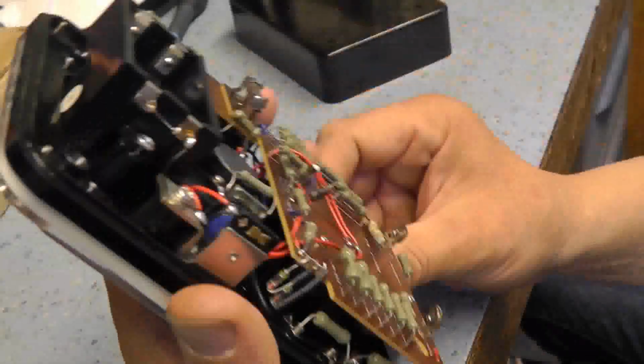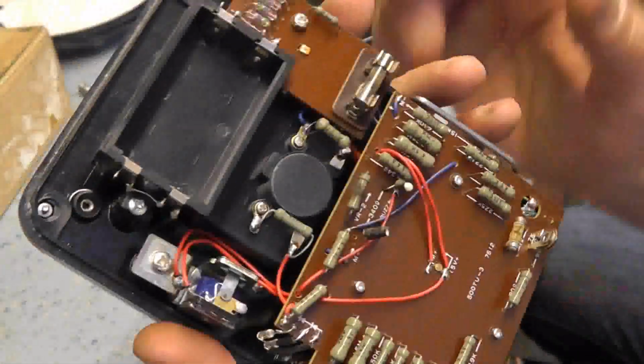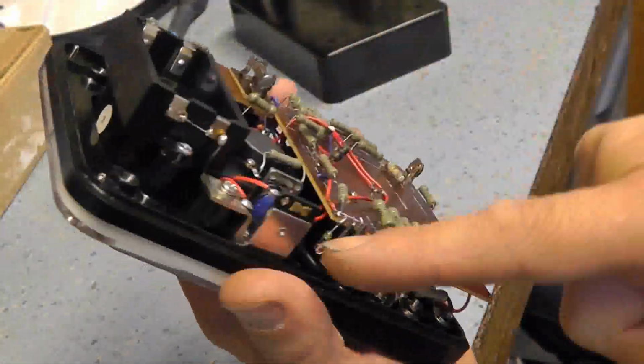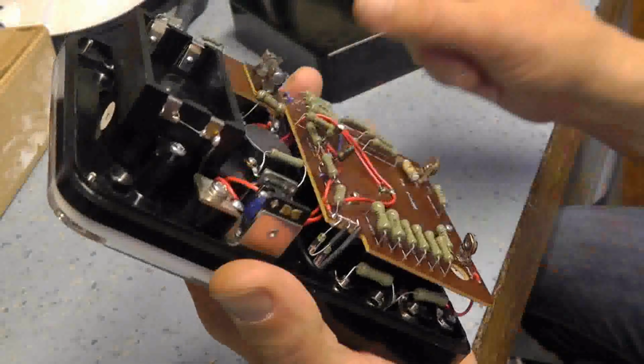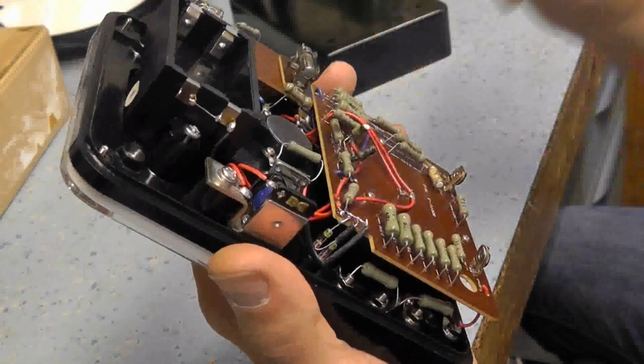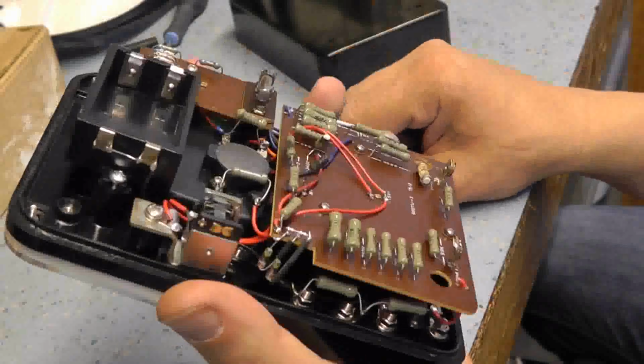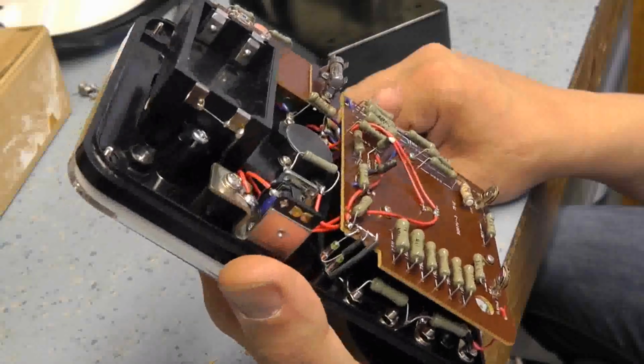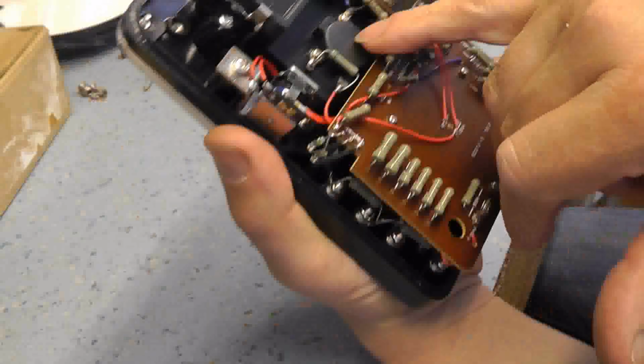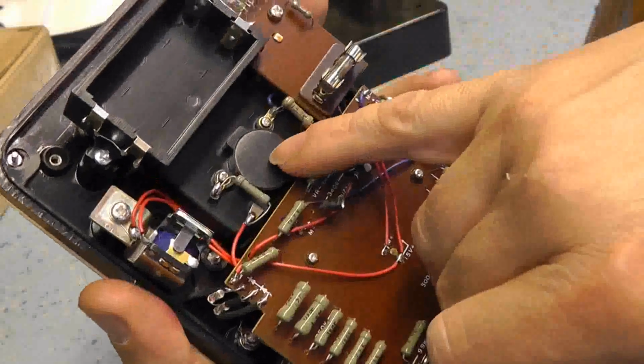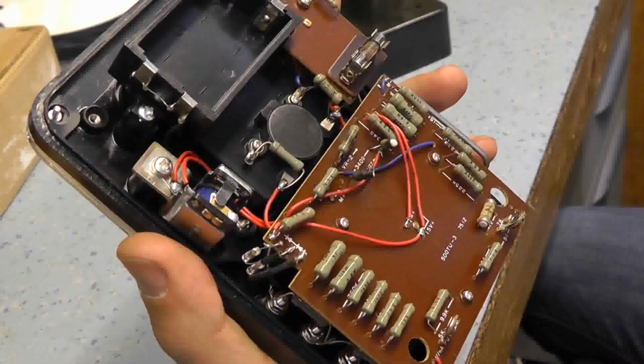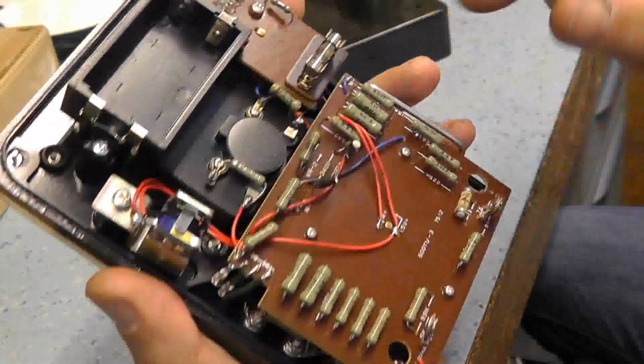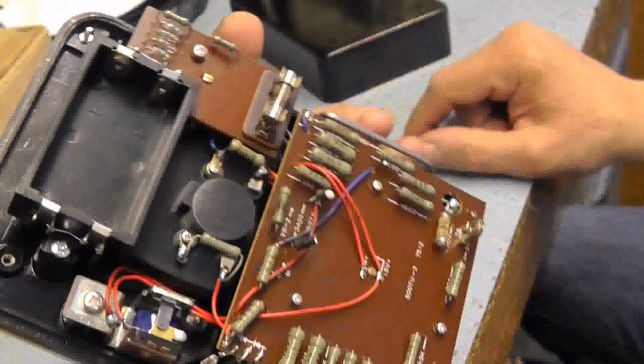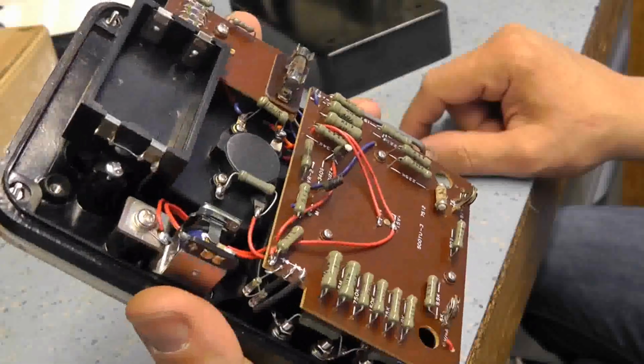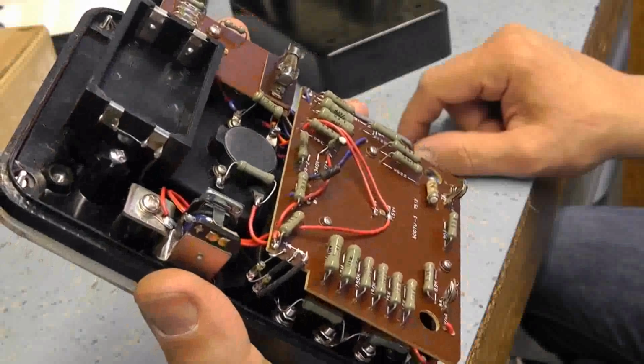Pretty nice condition inside, you know, no sign of any battery leakage, unlike the second unit that I've got. Here's the buzzer for the continuity, so it's a proper mechanical buzzer, none of your piezo sort of stuff. It's, you know, a mechanical buzzer that actually buzzes. Connections here to the meter, and series resistors to calibrate the meter. You'll see here that the fuse is popped, so obviously someone's given it some voltage at the wrong end, possibly in the ohms range or something like that.